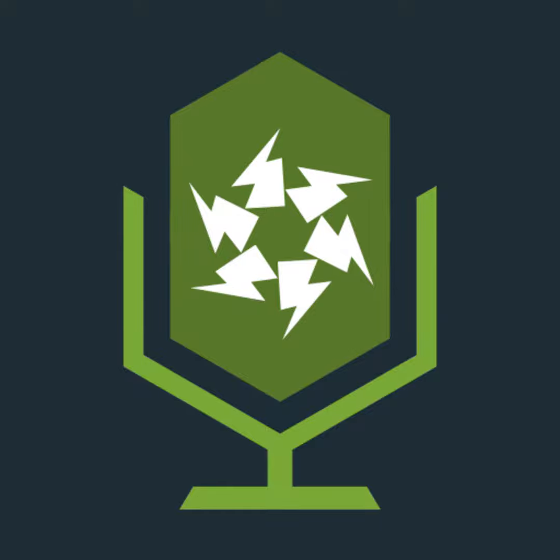And I know when Robin came on your podcast, it was a bit of an elephant in the room moment because he said, you know what, Dehn's philosophy is if you don't need to, don't fit that overcurrent protection device. In a domestic application where you've probably got an 80 amp head, 100 amp head max, our device for that application is called a Dehn guard, and without having a fuse in, just by way of manufacture, it has enough withstand capability to cope with 125 amps all day, so you don't need the overcurrent device. Has Dehn published any kind of spiel that gives electricians assurance on that?